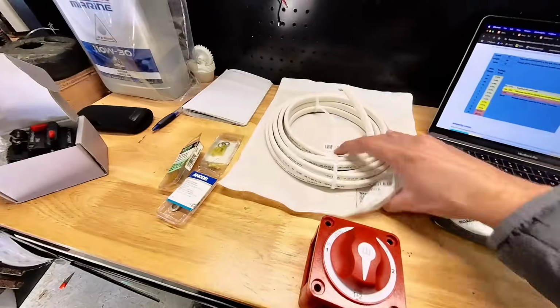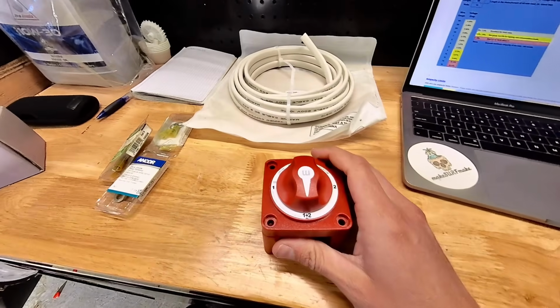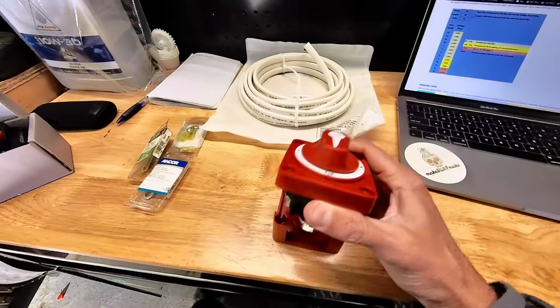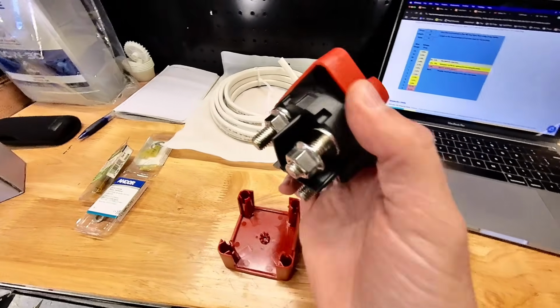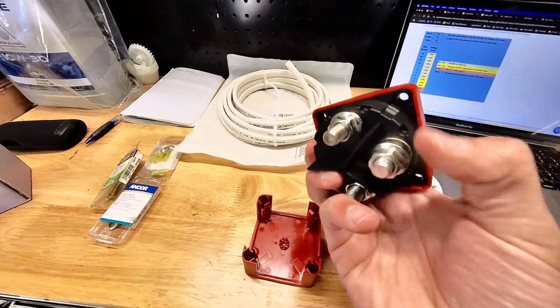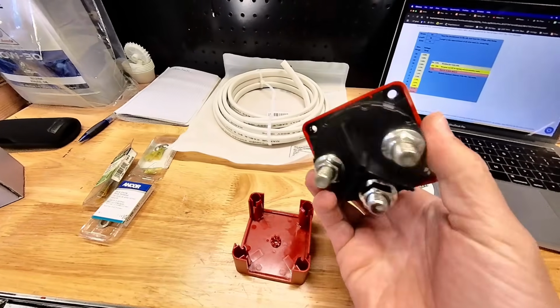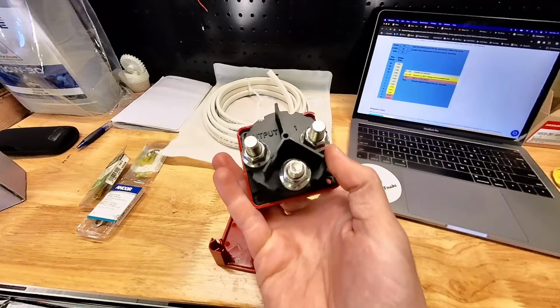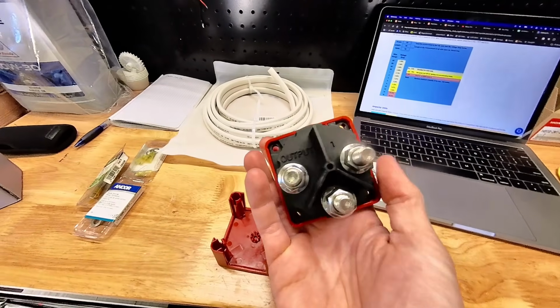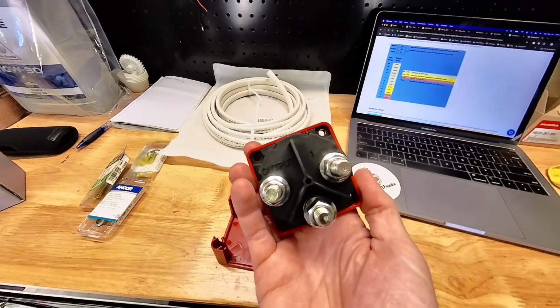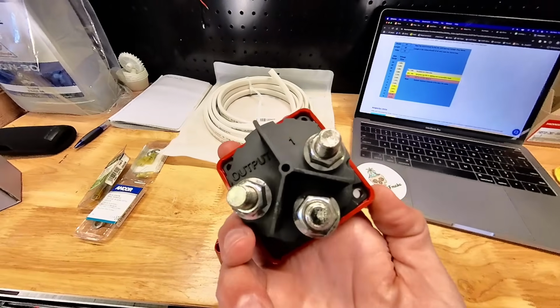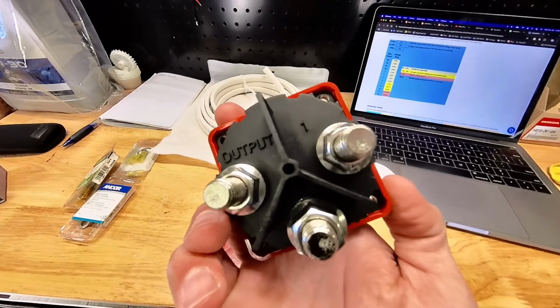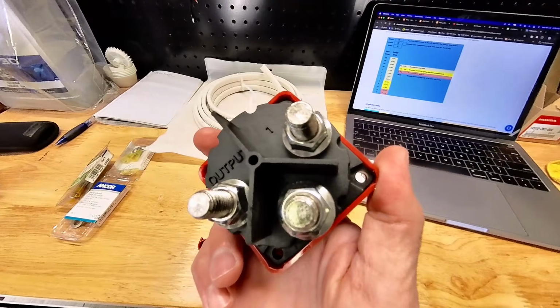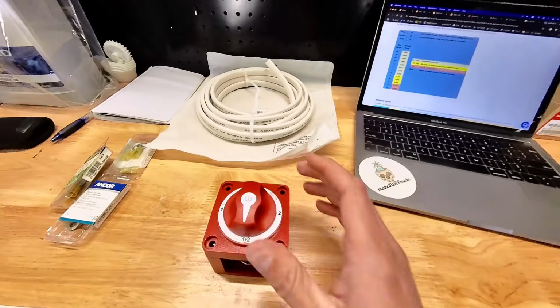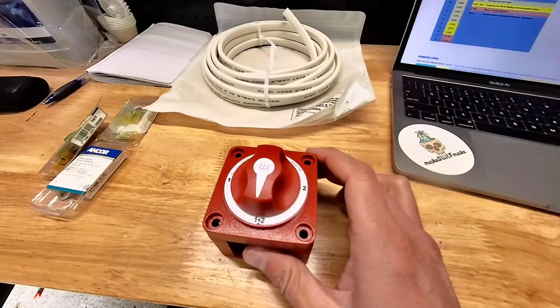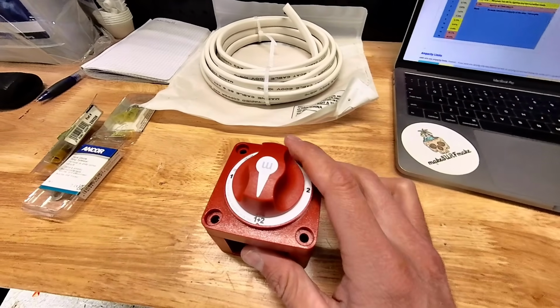Next thing we have is the new battery switch. This is a Blue Sea Systems 4-position battery switch. It's got some big giant fat lugs there. And this is a 3-pole one. They do sell some that have a 4th pole. I can't remember what the acronym for that is, but basically if you have a 4-pole one, it just means that you're able to switch to the off position while the engine's still running, without frying your charging system fuses. We don't have that. We've got a 3-pole. So it's very important that I remember never to turn this battery completely off and never disconnect the motor from the batteries while it's running.